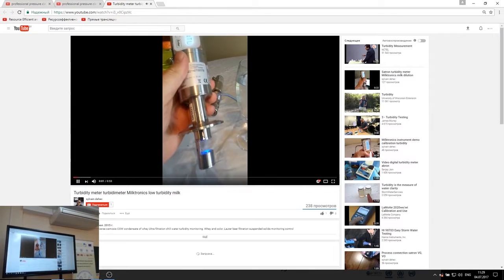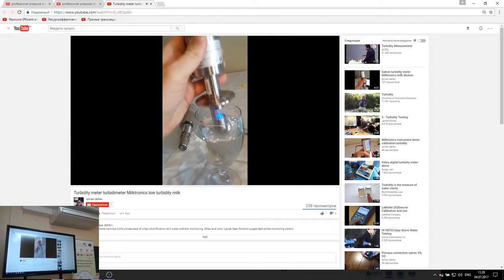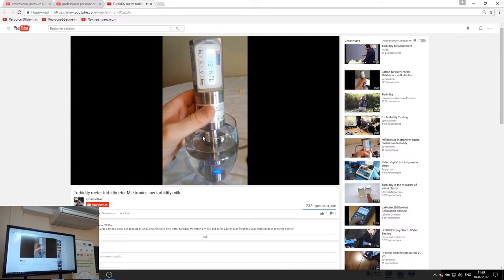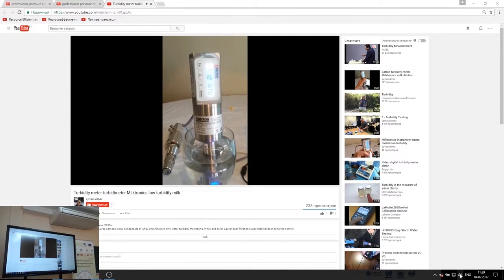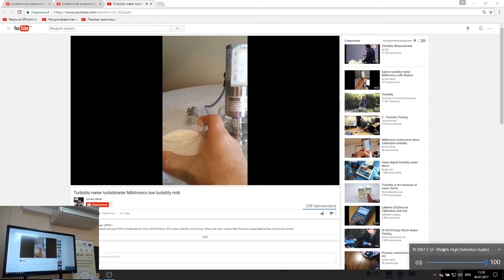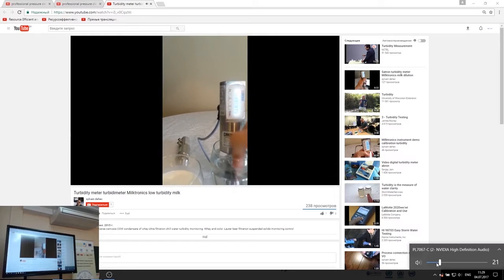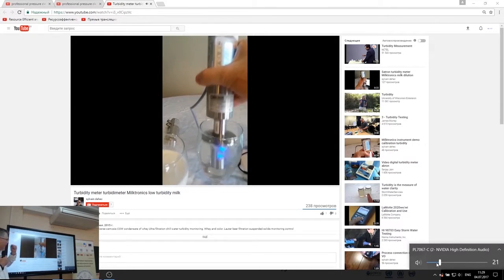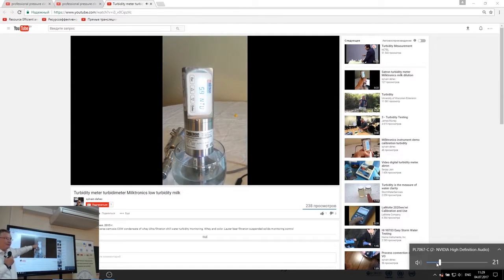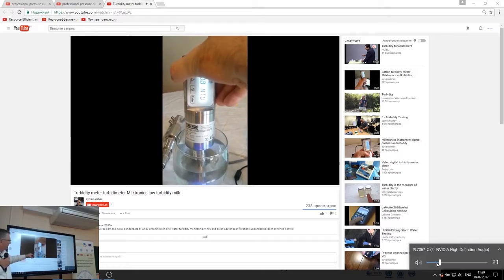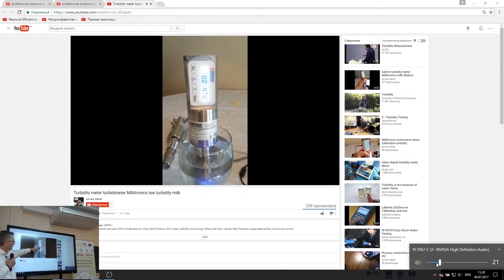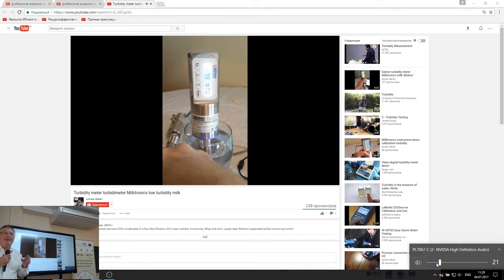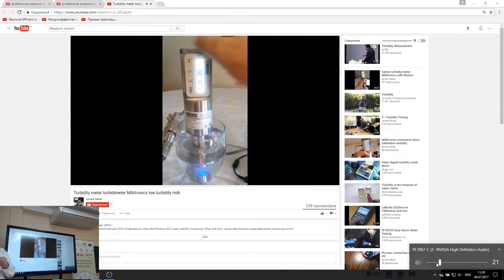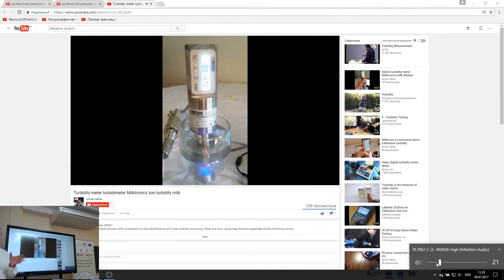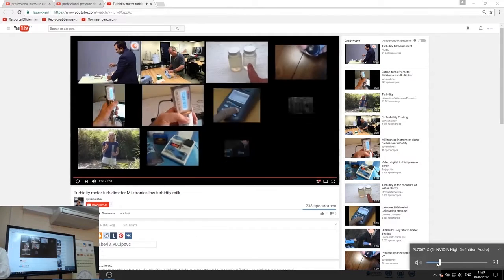This video now is on turbidity. This shows how a turbidity meter is working. This is the sensor, this is the scale, these are turbidity units. The guy started with clean water, and now he's adding milk drop-wise, and you see how the sensor reacts. It instantaneously detects turbidity caused by milk in water, so you can use this sensor very effectively to discriminate the milk front in a pipe from the water front.